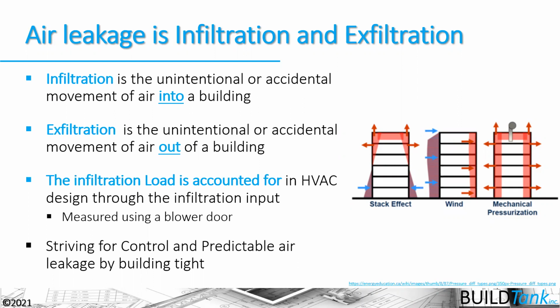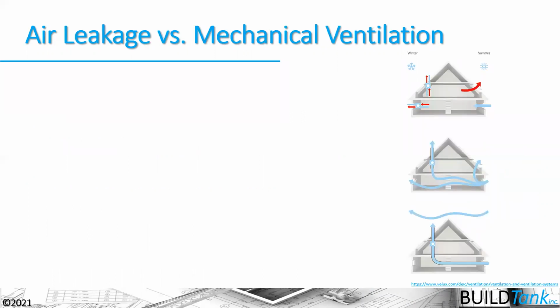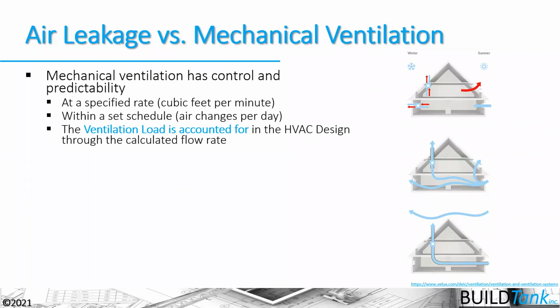And we take that into account when we do a Wrightsoft or an Elite load calculation for the house. But if we get control and predictability, we can lessen or lower the load that infiltration or air leakage has on our houses. Now, mechanical ventilation also has a load, and we take that into account as well. But ventilation air is predictable, and we have more control over it. We put it at a specific rate, so I know how many cubic feet are coming in to ventilate that house. We put it on a specific schedule or time. It can be continuous or intermittent ventilation, so I know exactly how much air is coming in to that house, and I can take that load into account when I'm sizing my HVAC system.